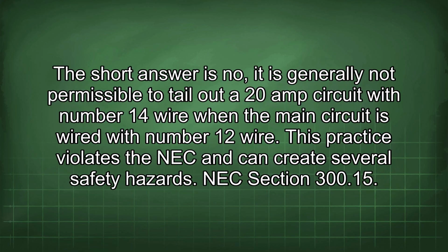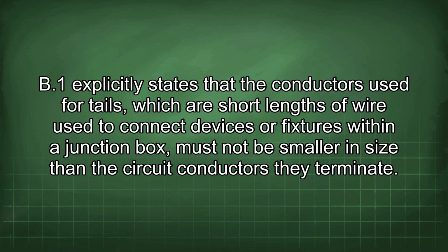It is generally not permissible to tail out a 20 amp circuit with number 14 wire when the main circuit is wired with number 12 wire. This practice violates the NEC and can create several safety hazards. NEC Section 300.15 B1 explicitly states that the conductors used for tails, which are short lengths of wire used to connect devices or fixtures within a junction box, must not be smaller in size than the circuit conductors they terminate.